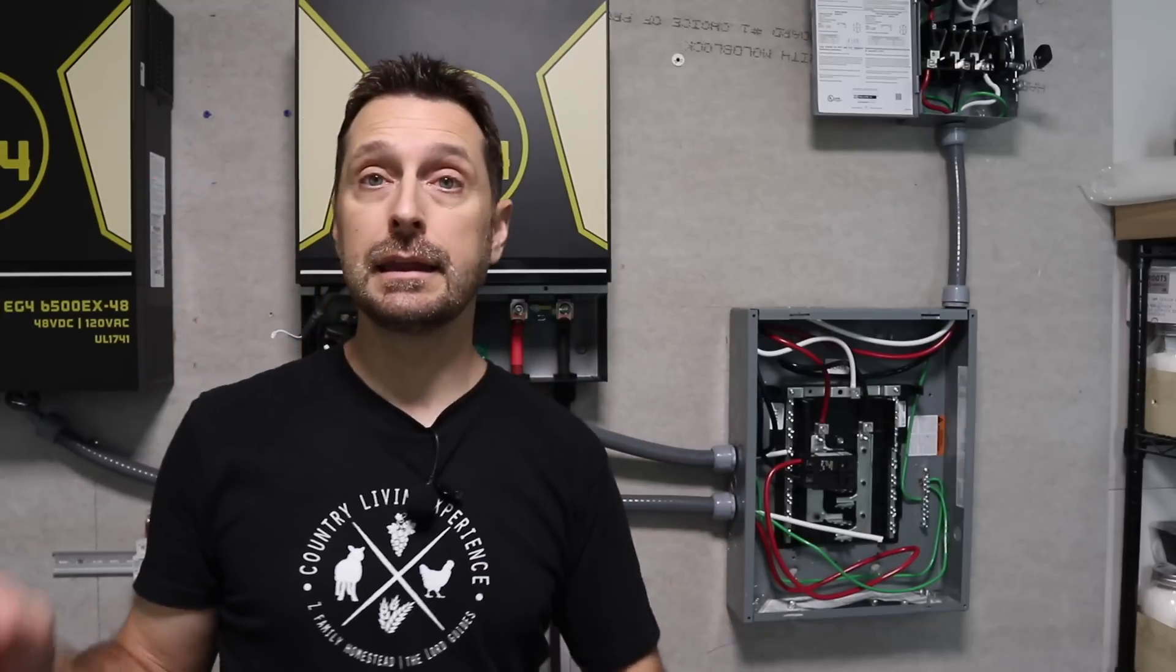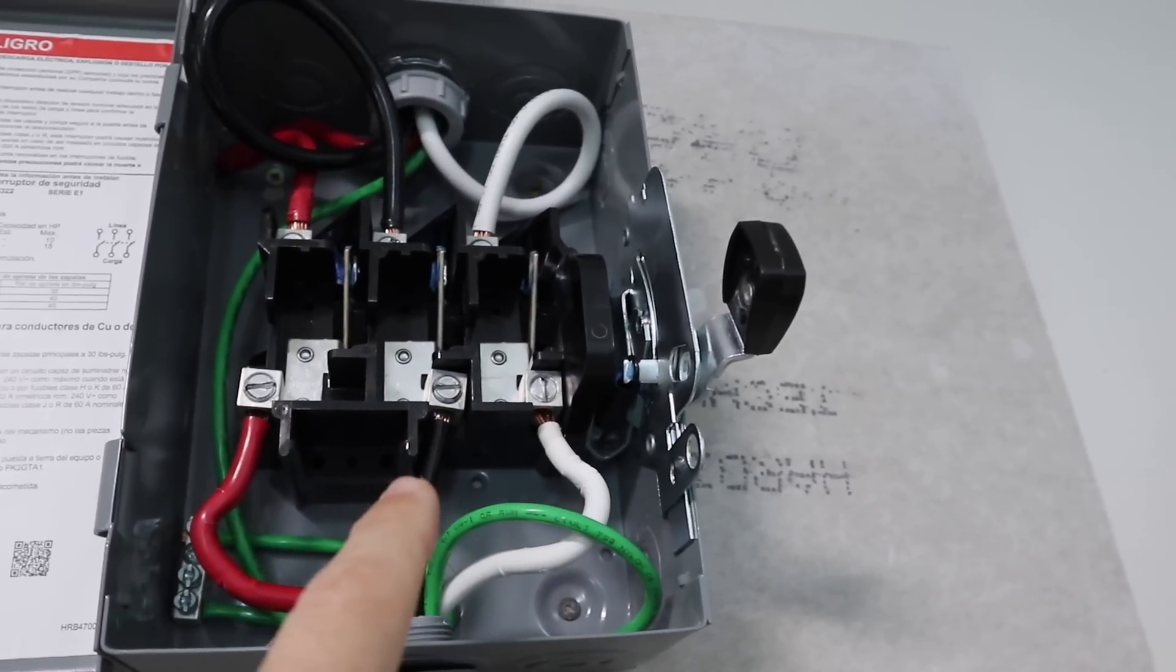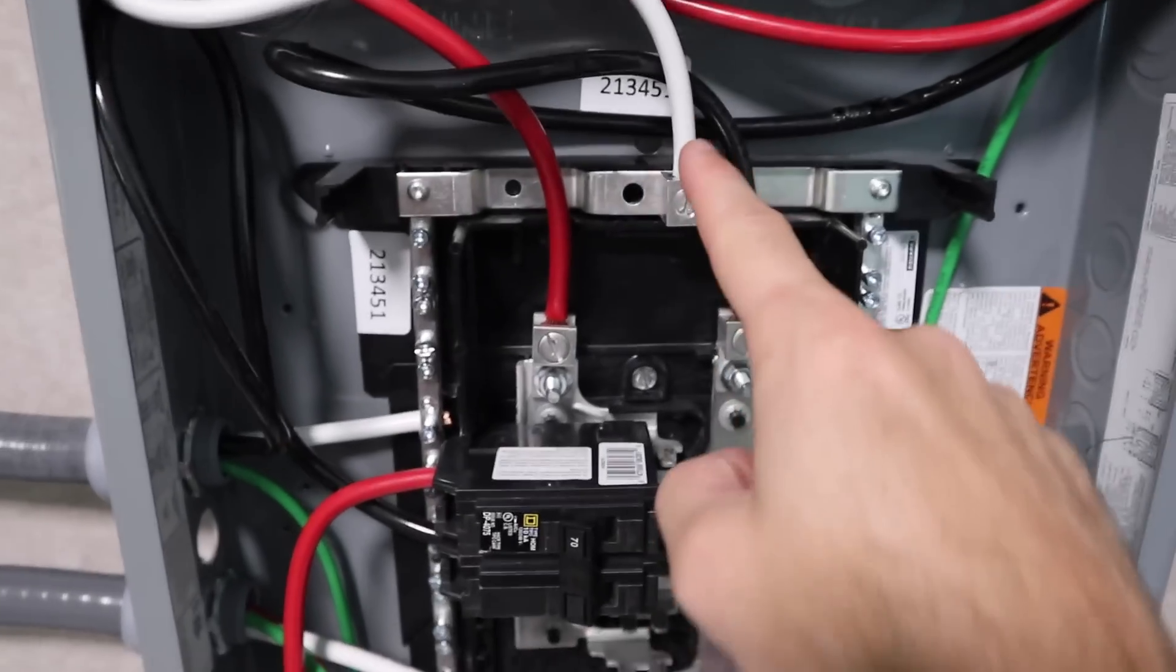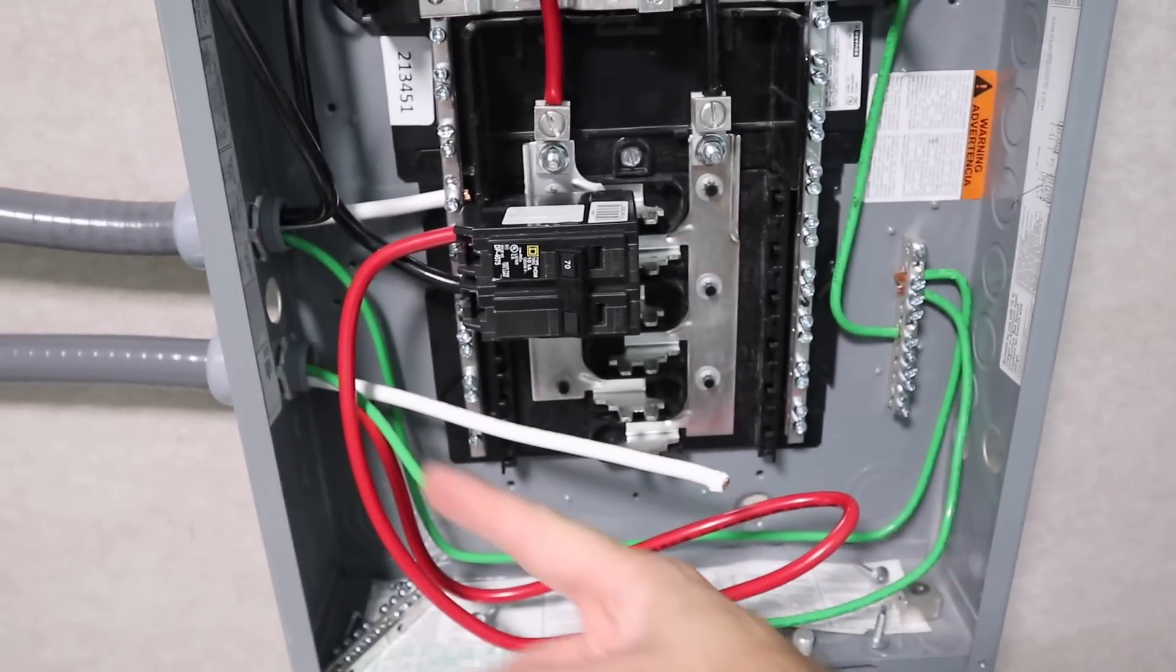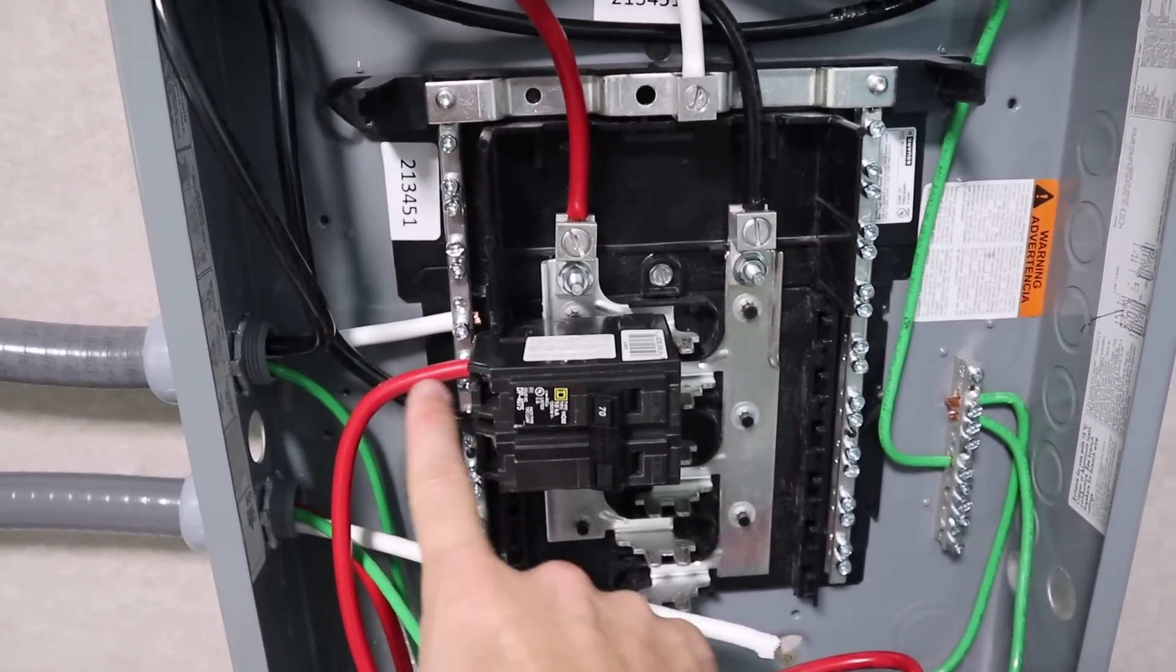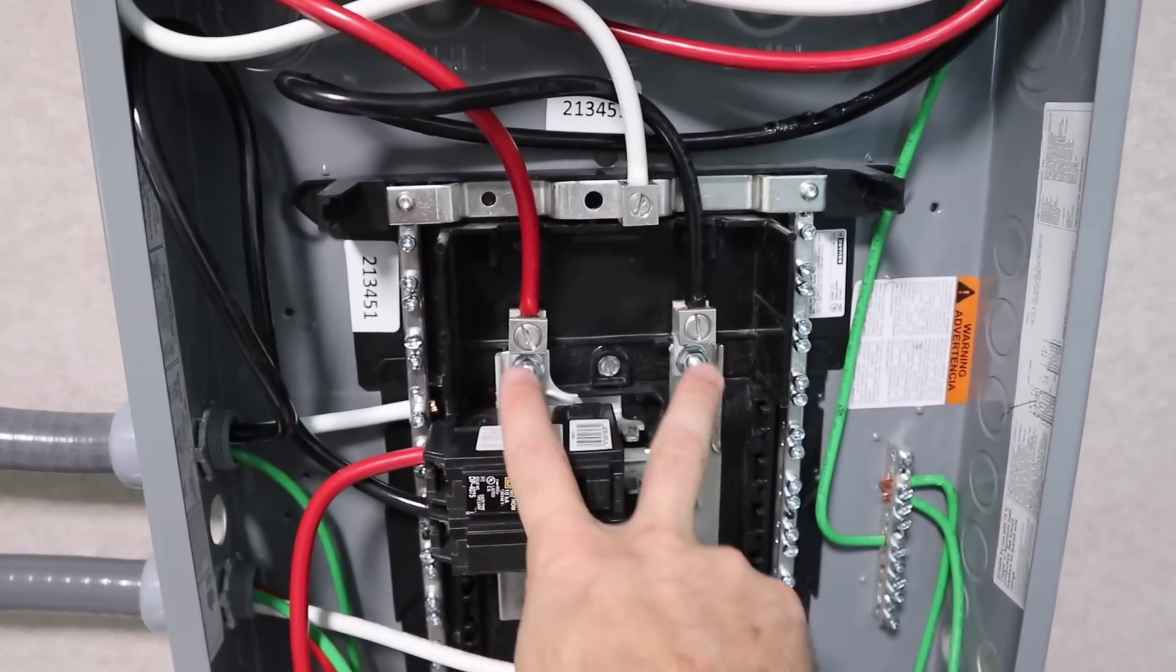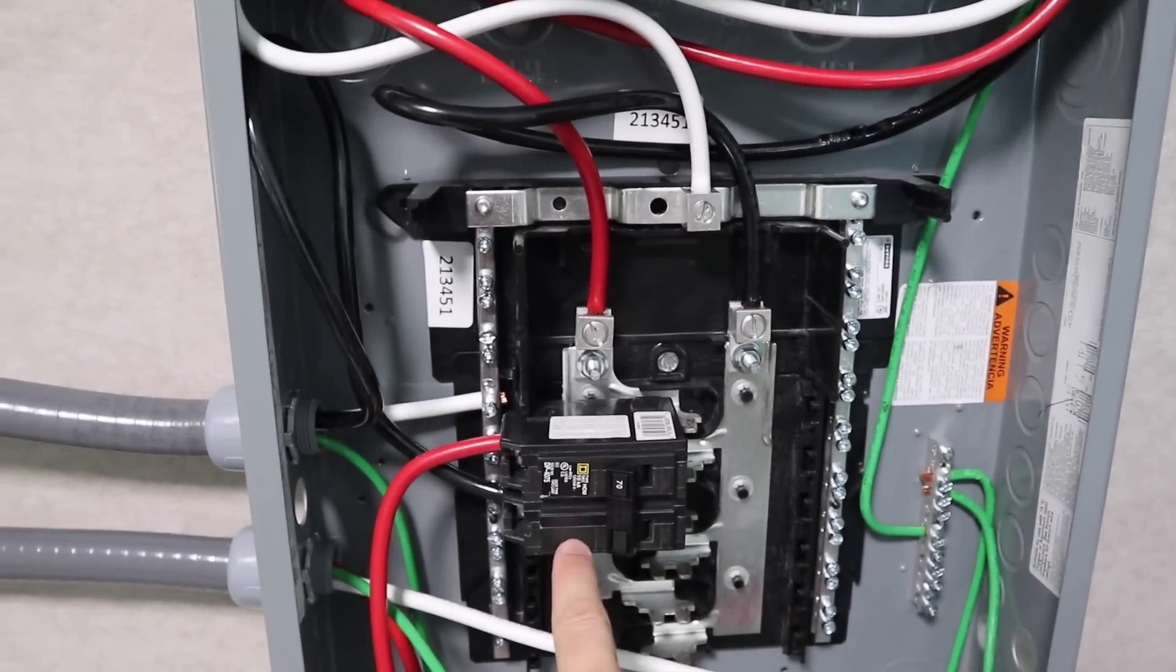Our wire is pulled down through the attic properly. We've got it cut, in our safety switch, in our panel and onto our first inverter. Let me show you what I did. Depending on which safety switch you get, neutrals to neutrals, line one to line one, line two to line two, grounds to grounds. Down into here, we've got our neutral on our neutral bar, grounds on our ground bar. These two grounds come over from each inverter. This is line one from one inverter, line two from the other inverter. I kept them separate color so I know by the color back to the main panel which one it is.